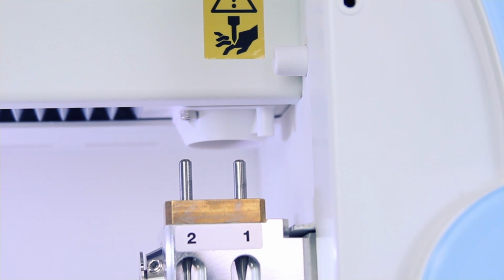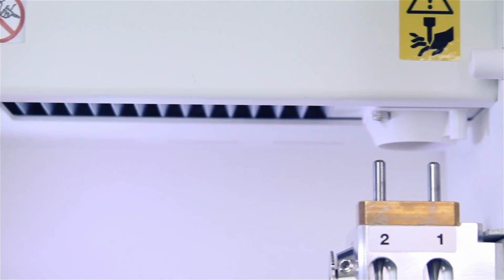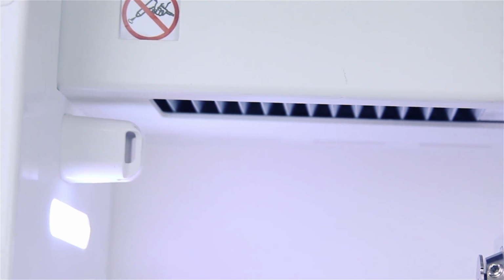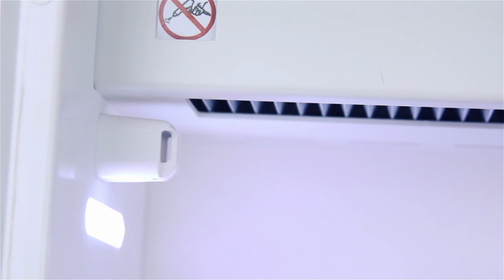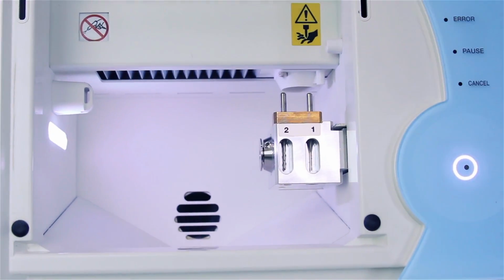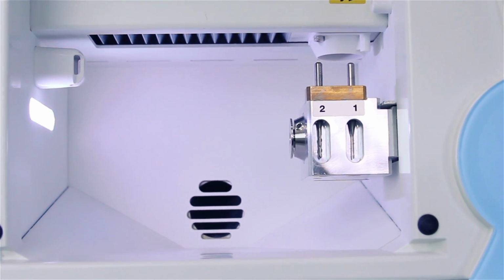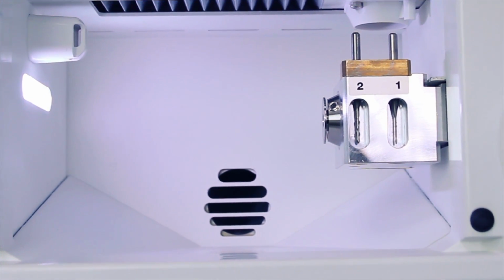The DWX-4's integrated air blower and a negative ion generator prevent excessive dust buildup when milling PMMA. A dust collection sensor prevents the machine from starting if the vacuum is inadvertently left off.